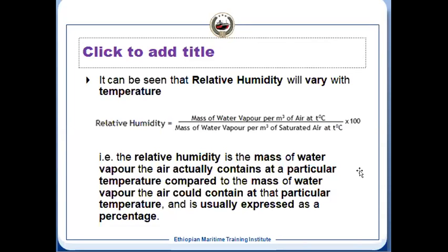Yes, it is. You are right that it is the cooling only. By cooling only, we dehumidify. So the only thing is at what temperature it will reach to dehumidify. It means you'll have to reach 100% relative humidity or the dew point, and then you'll have to reduce that further below the dew point. Then that process is called dehumidifying because the humidity is removed from the air.